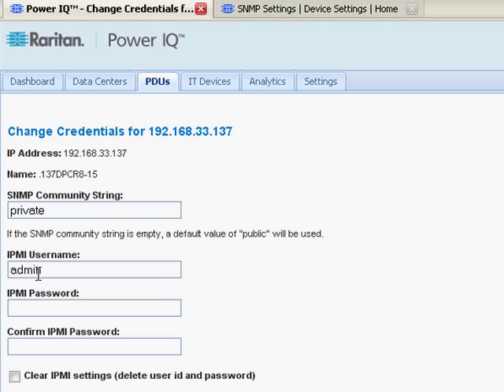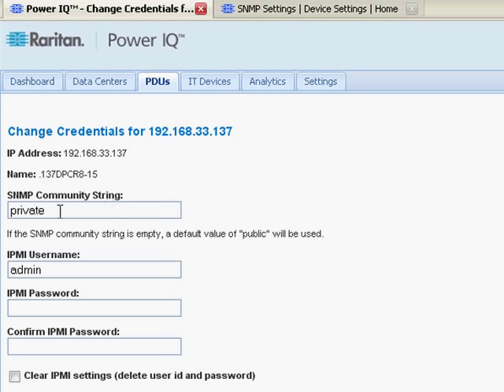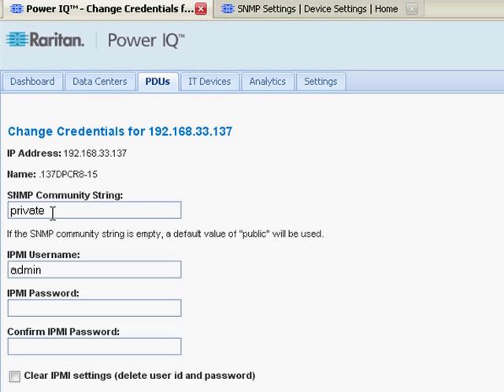In addition, the IPMI username, IPMI password, is actually the PX username and password. So for a Raritan Dominion PX, I need to enter the SNMP community string, private in this case, the username of the PX, and a password for the PX. If I was entering a third-party PDU, such as an APC metered PDU, or a ServerTech smart PDU, because PowerIQ is multi-vendor, all I would need to enter is the SNMP community string.